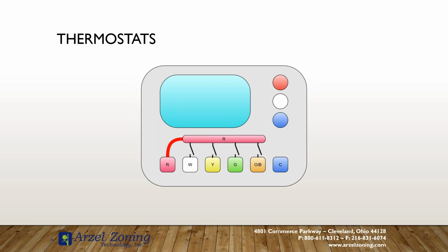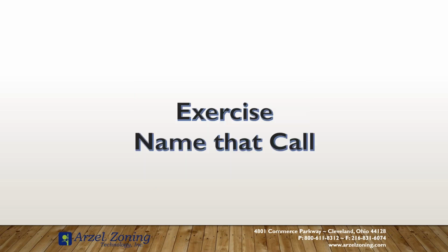So the thermostat is that starting point for all our controls. And just because the thermostat's calling for heating, just because it's calling for cooling, doesn't mean it's actually calling. And that's where we need to start our testing to verify that the thermostat is good. So in this example, it's pretty basic. We just have our RWYG O/B in common, and I have it drawn out with the relays for open. So as we start calling for things, we're going to see those relays change. So pay attention to the switches.